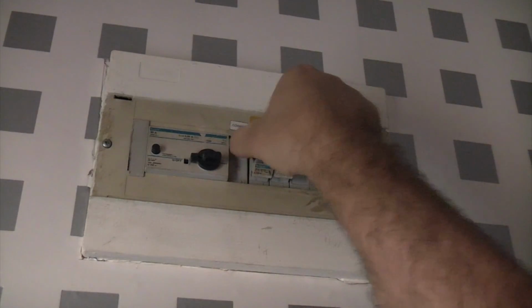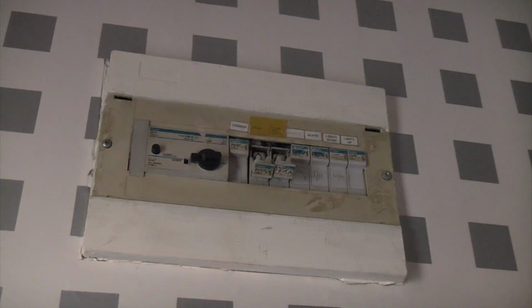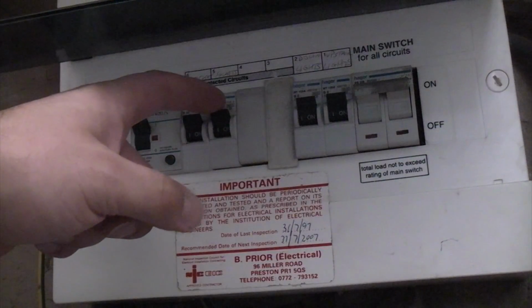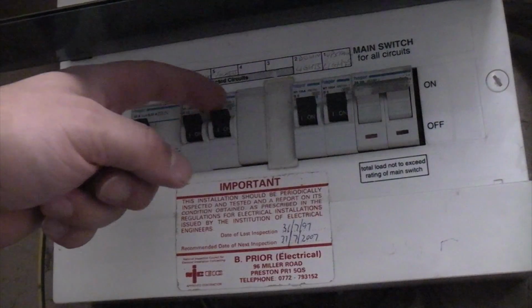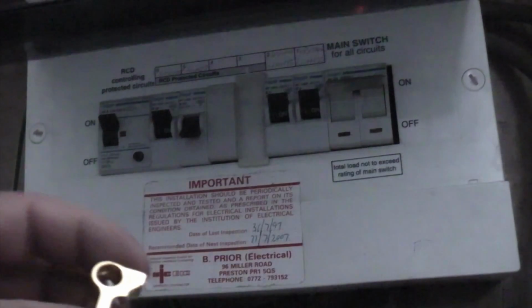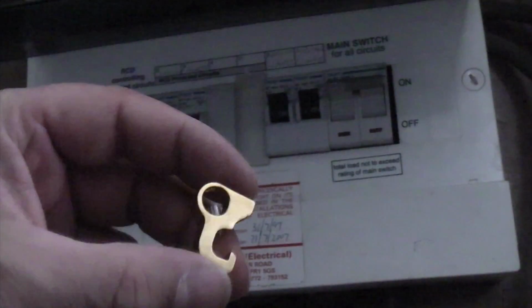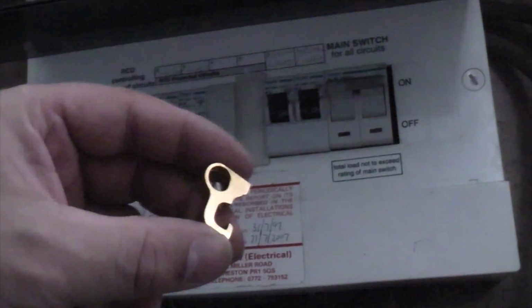Now I'm going to remove those two fuses and I'm going to keep them with me so that nobody can put them back in. If you have a modern consumer unit like this one that uses circuit breakers instead of fuses, you need to switch off the circuit breaker for the circuit that you're working on. But now we need to lock it off. So I'm going to use this device, which is specially made for locking off MCBs.